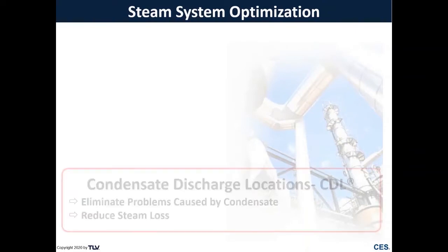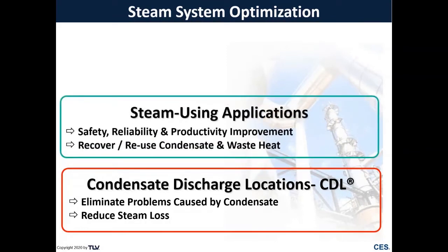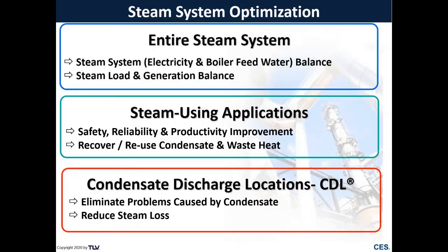If we look at steam system optimization, there are really three different phases. The first is managing and optimizing our condensate discharge locations, or CDLs — eliminating problems caused by backed-up condensate such as water hammer or decreased production, and reducing steam loss through leaking traps or open bypasses. The second is optimizing steam-using applications for safety, reliability, and productivity. The final step is optimizing the entire steam system balance, condensate recovery, and boiler feed water balance.